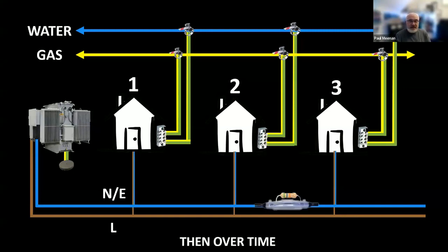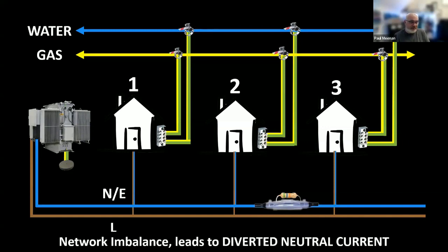And then after 50 years, 70 years, these cables will get old. They'll be jointed. The joints may not be good. And like with any loose connection, loose wires start fires. Now, over time, the impedance or resistance of your cable can go high. And what will happen is that the neutral, say from house 3, the return current, when it tries to go back to the substation, will meet a high resistance. So it won't want to go there. And this leads to a network imbalance, because what's going out is not coming back.